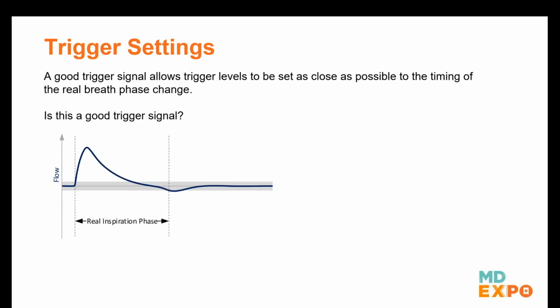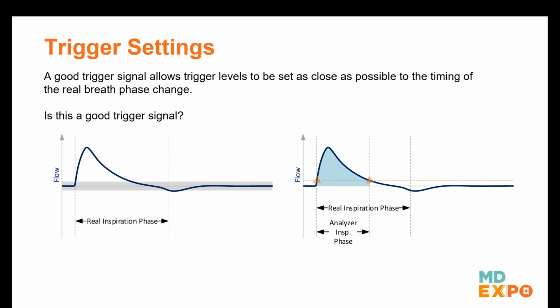So this is the first one. This is a flow signal, as you can see. These gray dashed lines indicate the real breath phase transitions. The first line is the start of an inspiration, and the second line is the end of the inspiration phase. The gray area around the 0 line is an area where we don't want to have our trigger levels, because a little bit of signal noise could then cause false triggering.